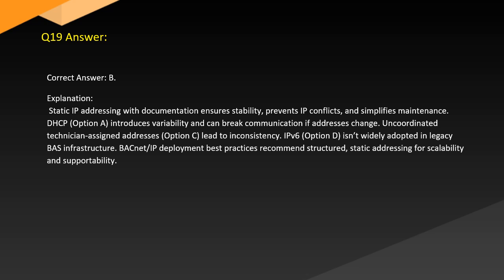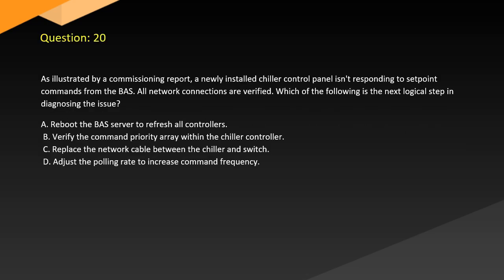DHCP, option A, introduces variability and can break communication if addresses change. Uncoordinated technician-assigned addresses, option C, lead to inconsistency. IPv6, option D, isn't widely adopted in legacy BAS infrastructure. BACnet deployment best practices recommend structured, static addressing for scalability and supportability. Question 20. Illustrated by a commissioning report, a newly installed chiller control panel isn't responding to setpoint commands from the BAS. All network connections are verified.